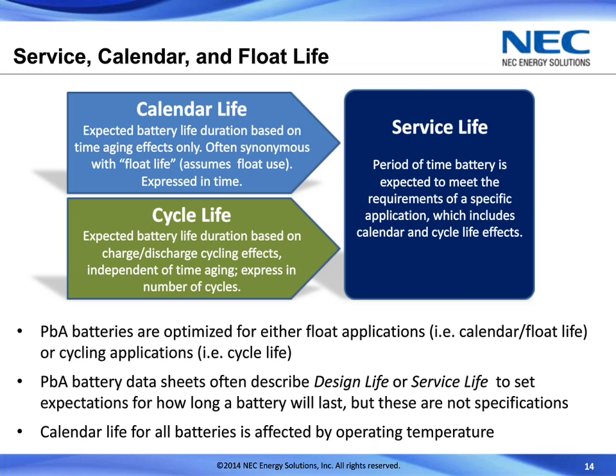These two things combined is what really determines the service life, and the service life is really how long that battery will last in the given application. That is some combination of calendar life and cycle life. Now, most lead-acid batteries are really optimized for one or the other application. They're either optimized for what's called float service or backup service, or they're optimized for some sort of cycling, let's say a deep cycling battery or something that's been meant to do that type of application. There may be batteries that are compromises in between, but they usually end up not being able to do either one in a particularly good way, or at least not as good as one that is optimized for the given application.